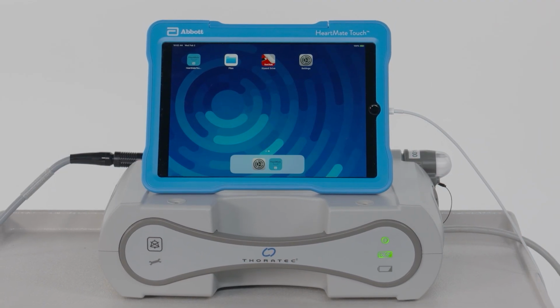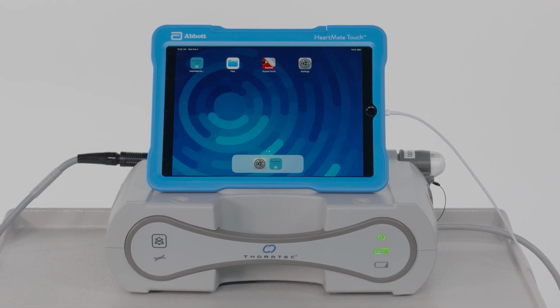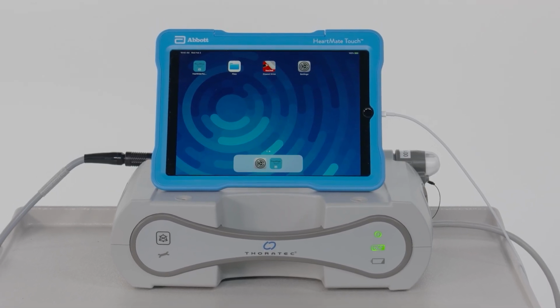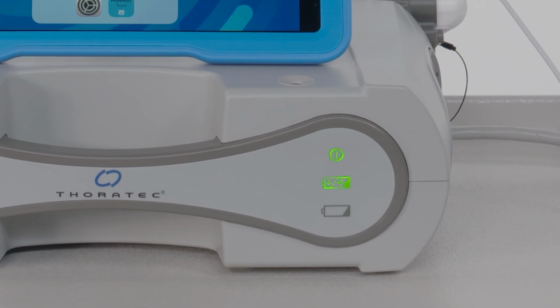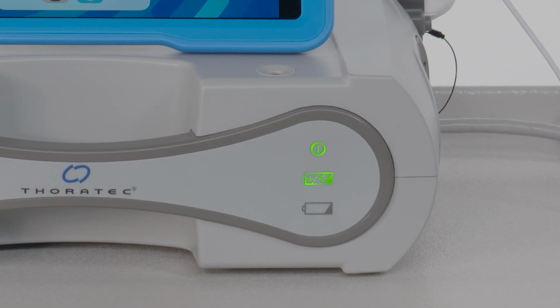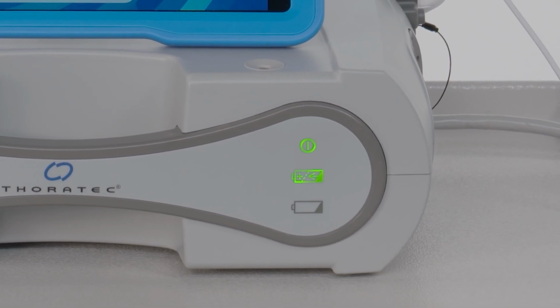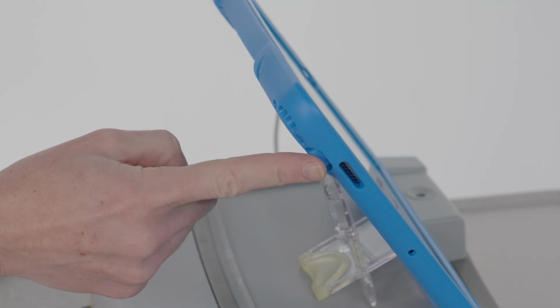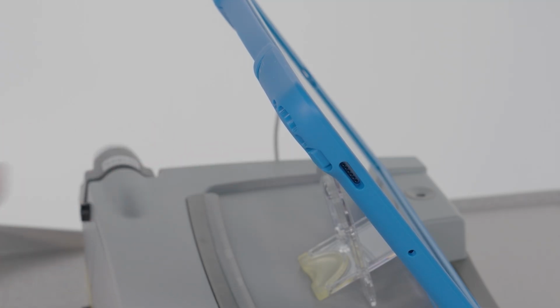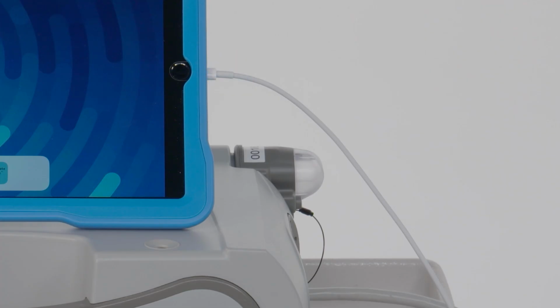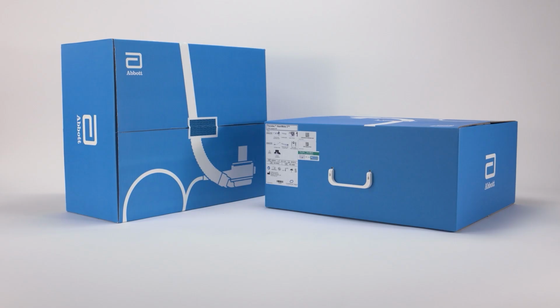During implant, the HeartMate 3 left ventricular assist device must be operated with the power module and the HeartMate touch communication system. Make sure the equipment, the power module with patient cable and HeartMate touch wireless adapter are set up and powered on. Ensure the HeartMate touch tablet is turned on and fully charged. It should be plugged into an outlet during the implant procedure. A backup system should be nearby if needed.